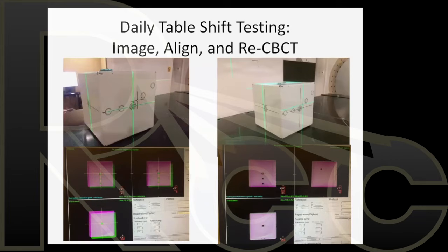Table shifts, as I mentioned, are extremely important in radiation therapy. Image guidance really is based upon accurate targeting of the tumor and then shifting the table to that point. Now, on this object, you have the isocenter here, but you also have an object here. So what you can do is take an image of the object, KV image, anterior and lateral, target that object that's off center, use the software to shift the table to that position, and then re-image it. Very, very important test to make sure that your table shifts are going in the right direction and that your targeting system is working correctly.